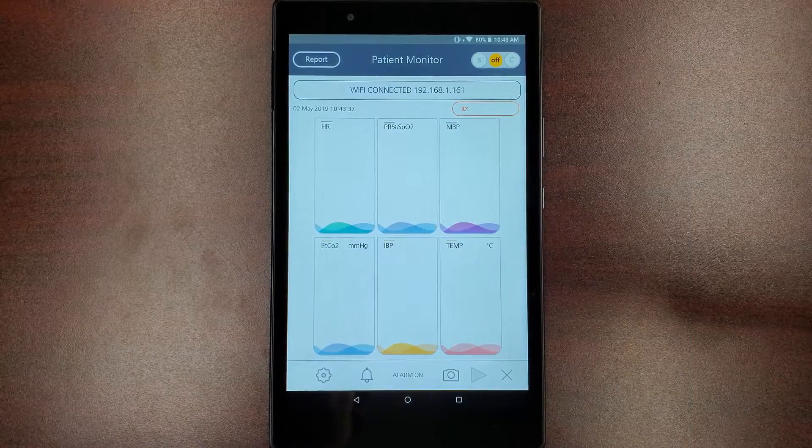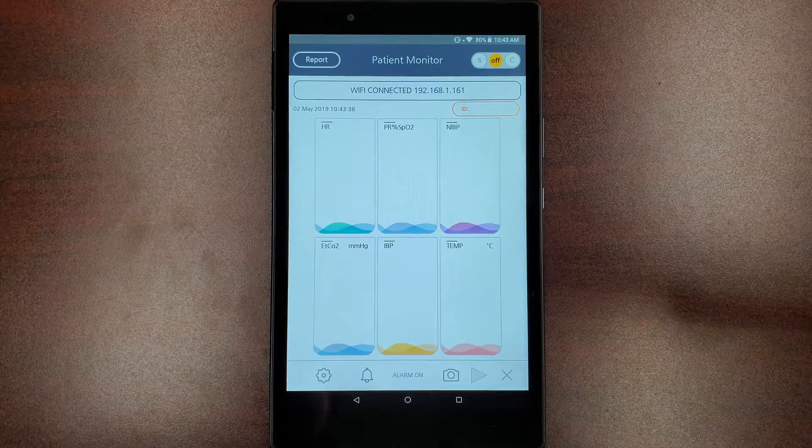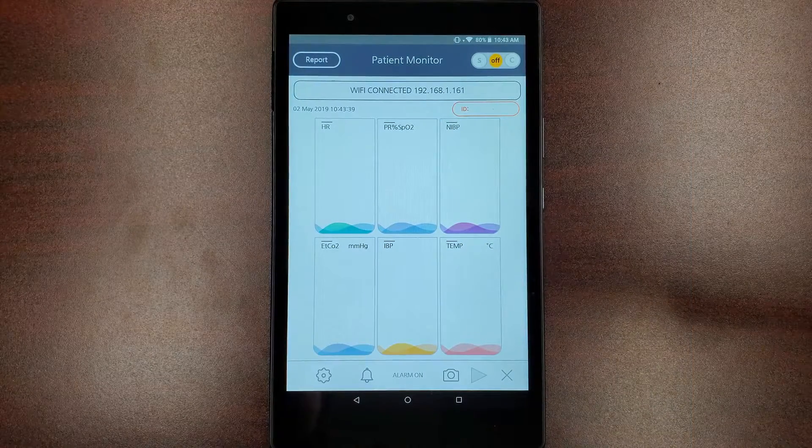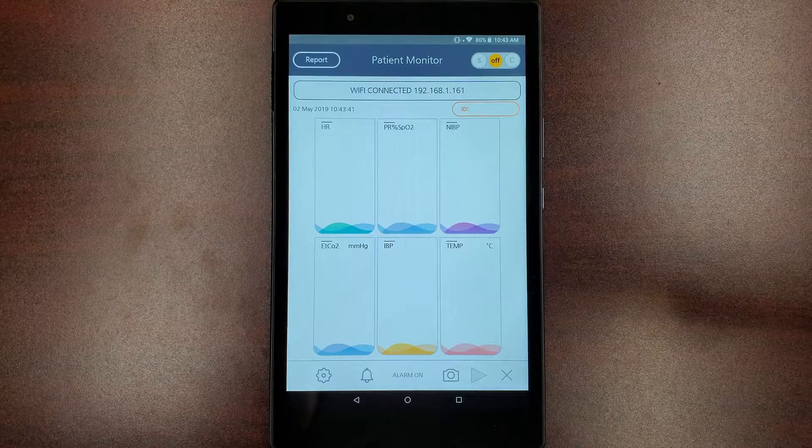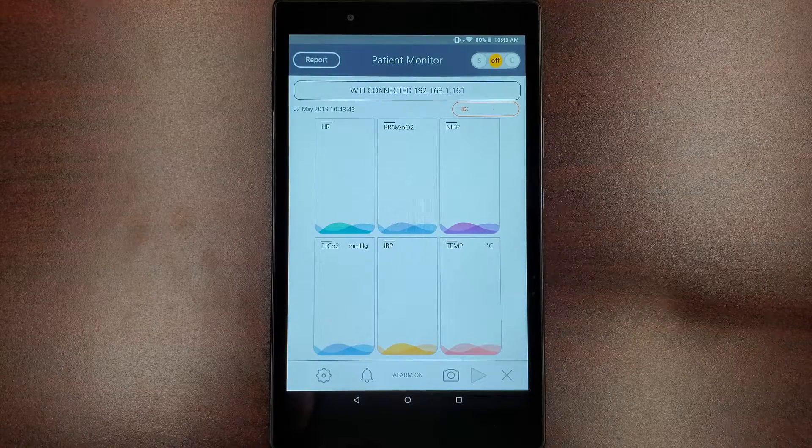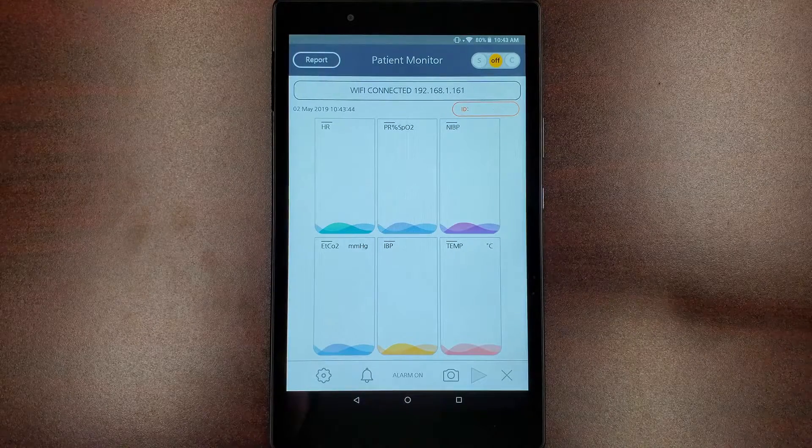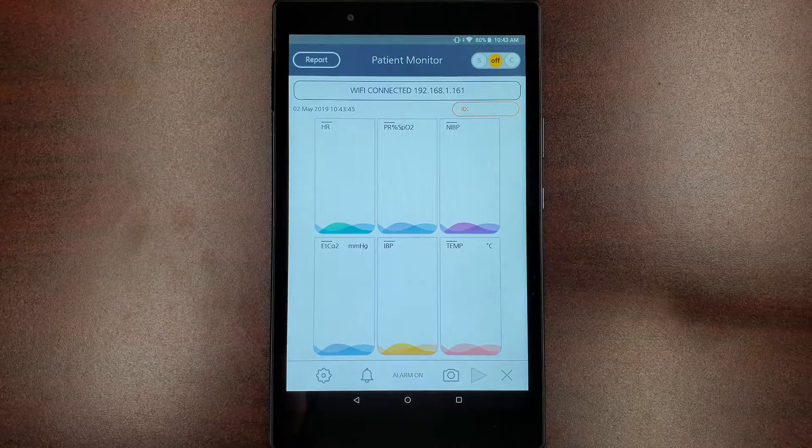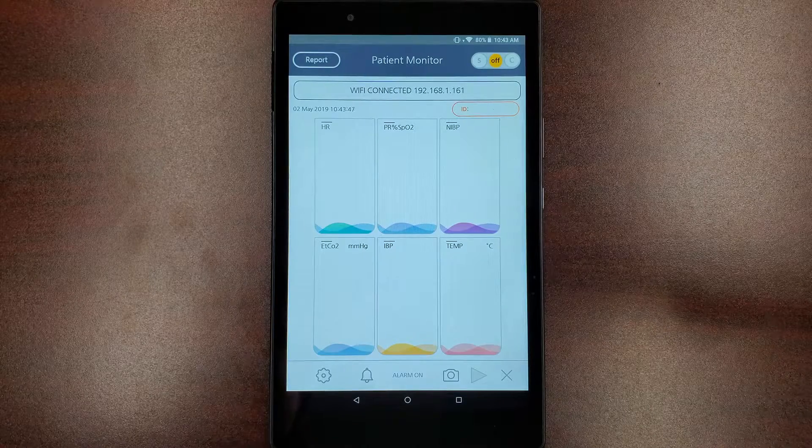Client mode is best used when you would like several mobile devices to access data from a patient monitor. This mode connects multiple mobile devices through the use of the BT Link computer software on a desktop computer.